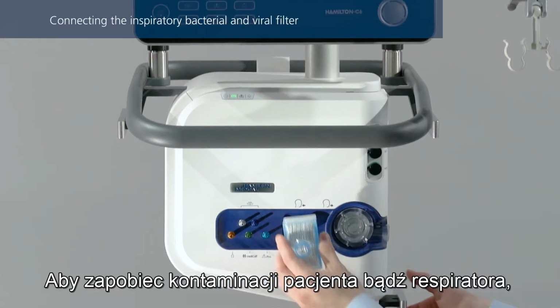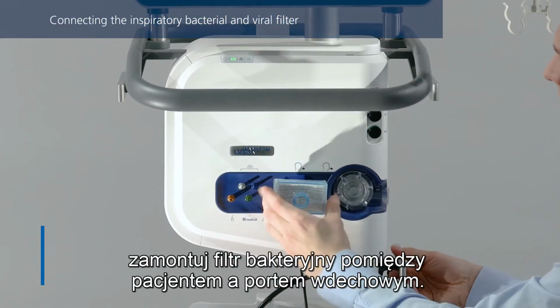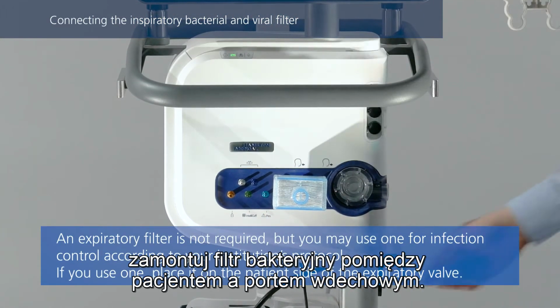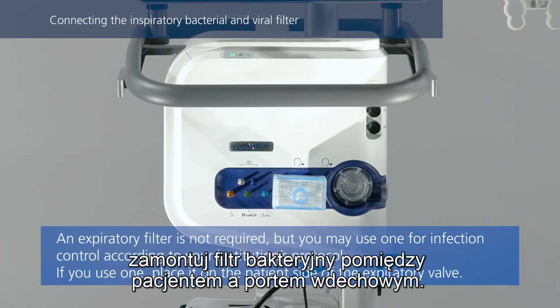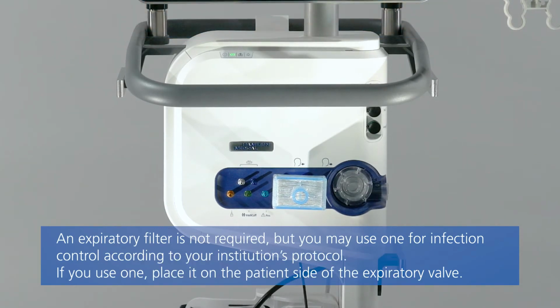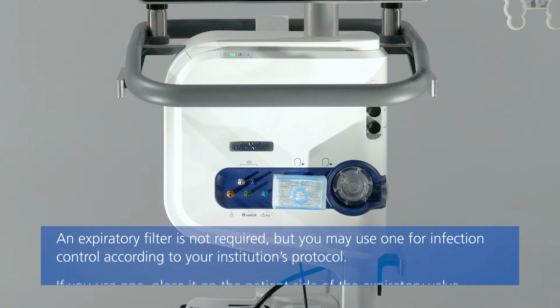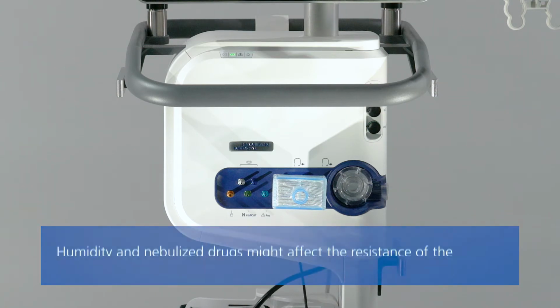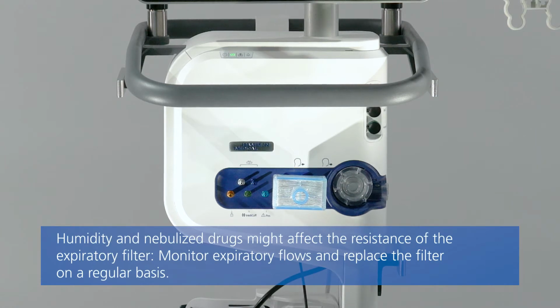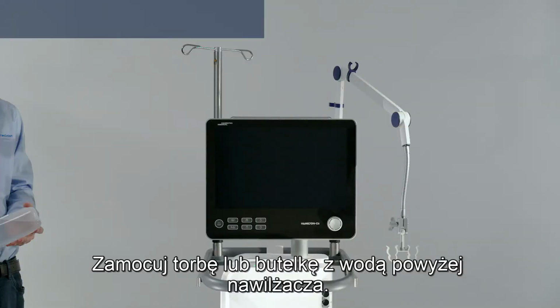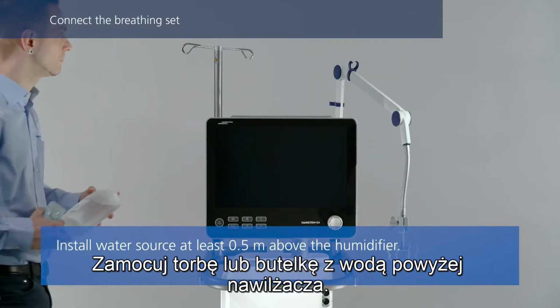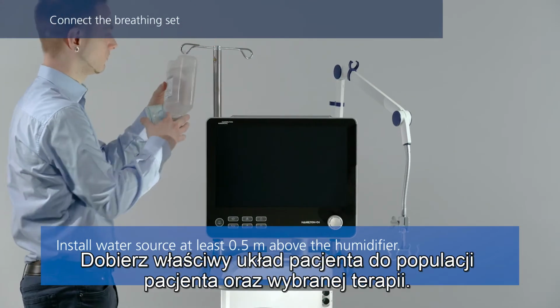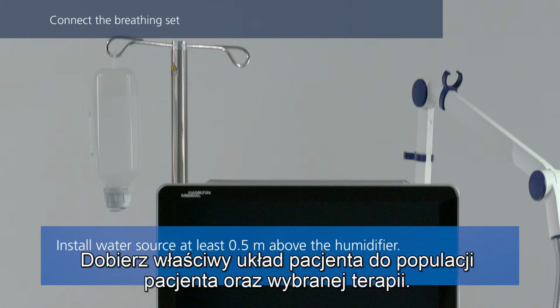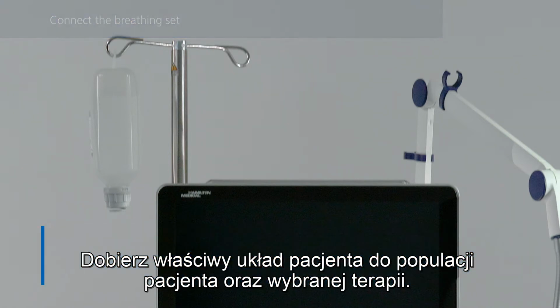To prevent patient or ventilator contamination, connect a bacterial and viral filter between the patient and the inspiratory port. Install a water bag or bottle above the humidifier. Choose the correct breathing circuit according to the patient group or selected treatment.